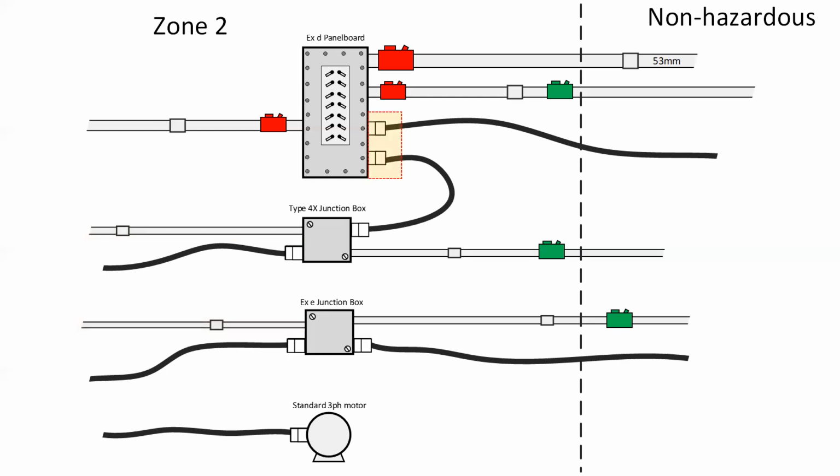The cables which enter into the explosion proof panel board are identified under 18-154, and we can see subrule 4 indicates specifically that where the cable enters in, if it's explosion proof, it needs to be EX or explosion rated. The connectors on my type 4X junction box are not listed within 18-154.